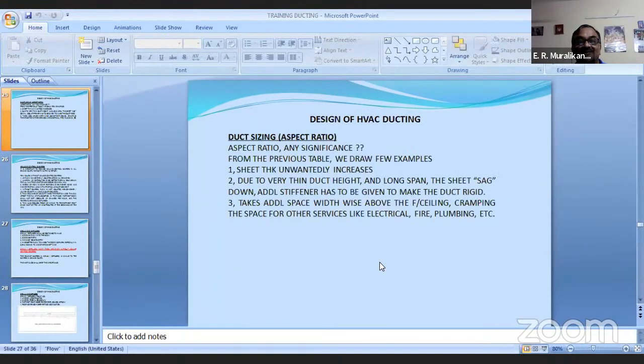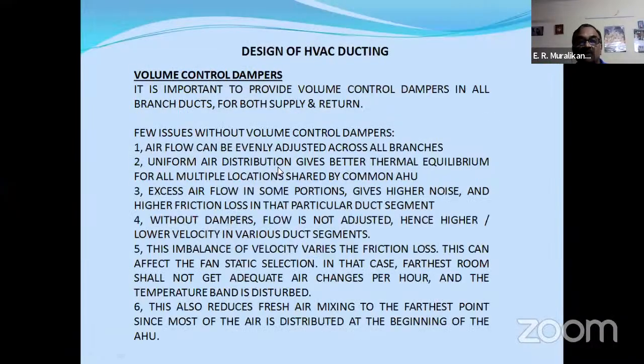Now, the aspect ratio we saw, correct? Now, volume control dampers. It is important to provide volume control dampers in all branches for both supply and return. A few issues arise without volume control dampers. Airflow cannot be evenly adjusted across all branches. Uniform air distribution gives better thermal equilibrium for all the multiple locations shared by a common AHU. Excess airflow in some portions gives higher noise and higher friction loss in that particular duct segment.